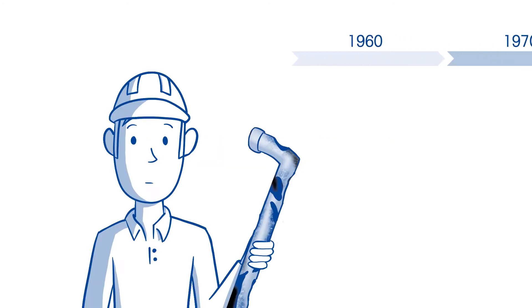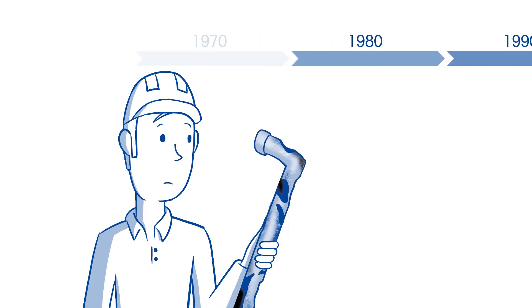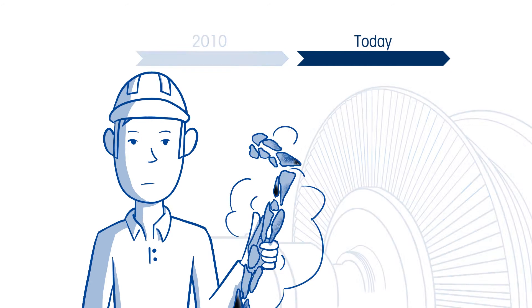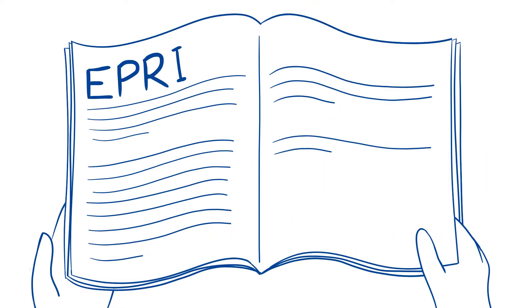For decades, power plants have been trying to control chloride and sulfate contamination that can cause corrosion and other damage to expensive equipment. Concentration limits of 2-3 ppb for chloride and sulfate are even specified in industry guidelines.